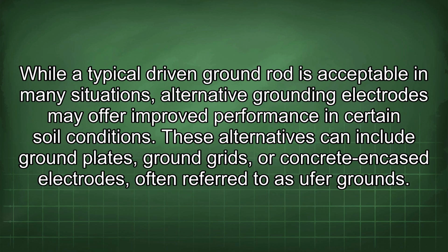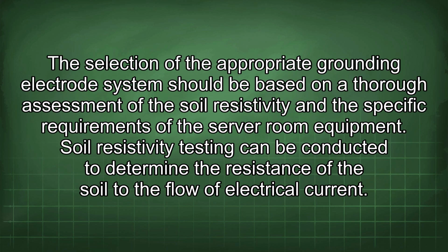One should also consider the type of grounding electrode system used. While a typical driven ground rod is acceptable in many situations, alternative grounding electrodes may offer improved performance in certain soil conditions. These alternatives can include ground plates, ground grids, or concrete encased electrodes, often referred to as UFER grounds. The selection of the appropriate grounding electrode system should be based on a thorough assessment of the soil resistivity and the specific requirements of the server room equipment.